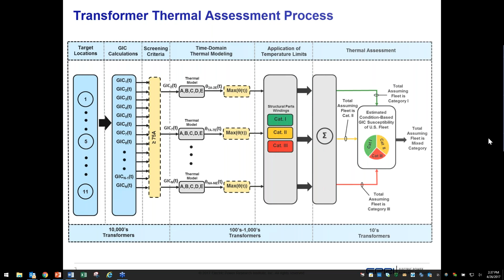The ending results of that were really somewhat remarkable given where we are at the state of knowledge right now. We would not expect a large failure rate in these major bulk power transformers. In fact, the lowest number that we achieved was 3 of 37,000 based off a single blast location. The highest number that we reached was 14 based off a different blast location. So even the worst case scenario for a single blast was 14 transformers which would approach that level of damage. It doesn't say that they would actually reach damage, but it does say that they would have temperatures that we should be concerned about for potential damage. So I say all that to say that failure of a large number of bulk power transformers, in the hundreds, from an E3 seems unlikely based off of this information.